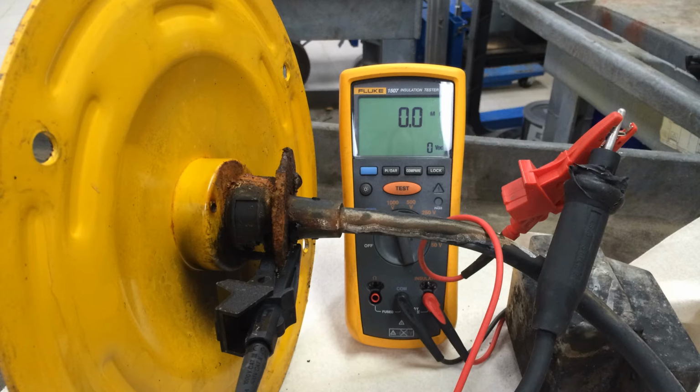This is also a good example of how a field isolation transformer can give you a bad meg reading on your circuit. The fixture is bolted directly to the ground system, and the circuit is directly connected to the fixture.